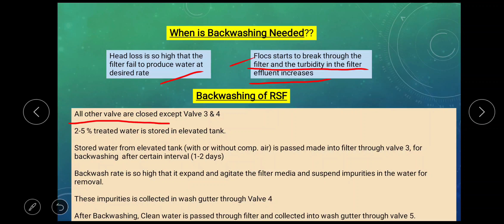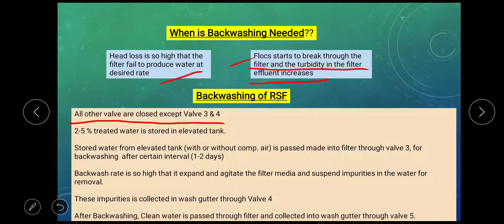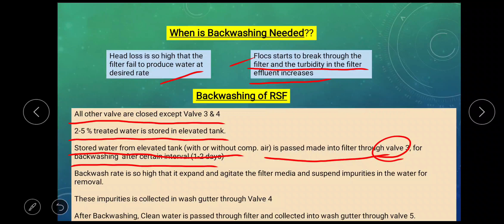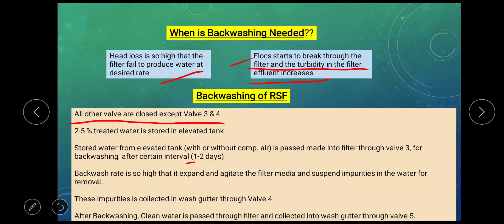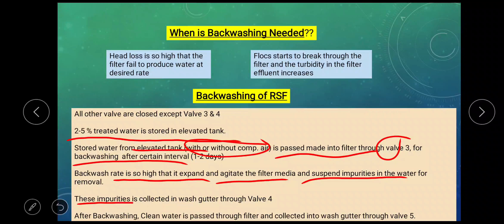All other valves are closed except valve number 3 and 4. Two to five percent of the treated water is stored in an elevated tank, so only 2 to 5 percent of the filtered water is stored for the cleaning operation. Stored water from the elevated tank with or without compressed air is passed into the filter through valve number 3. Back washing is done every 1 to 2 days. The back washing rate is so high that it expands and agitates the filter media and suspends impurities in water for removal. These impurities are collected in the wash gutter through valve number 4. After back washing, clean water is passed through the filter and collected into the wash gutter through valve number 5.